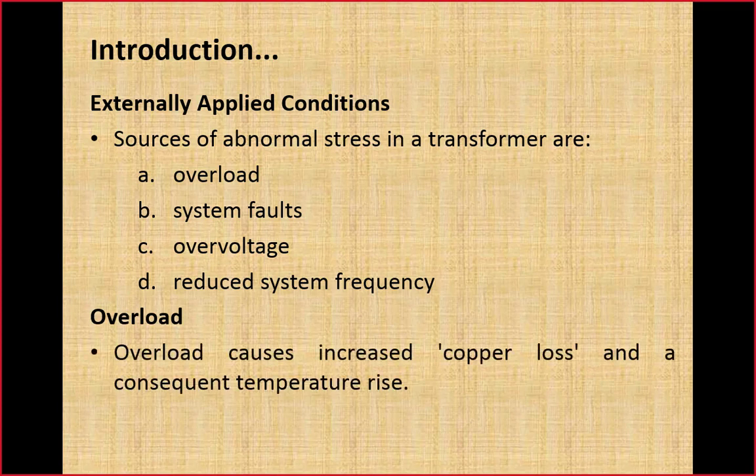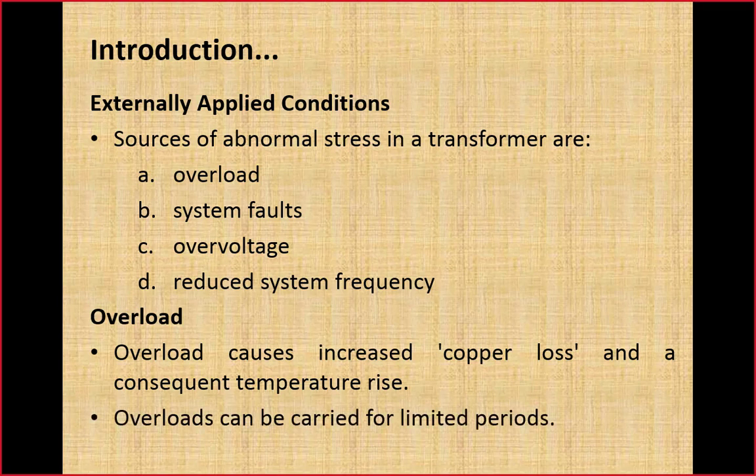So how will this overload affect the transformer? Overload will result in a higher amount of current passing through the transformer windings, that will cause an increase in I square R losses, copper losses inside the transformer winding, and result in a rise in temperature. Remember, these power transformers and distribution transformers are designed to carry this overload for a limited period.